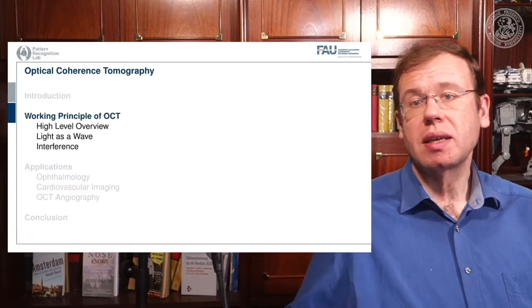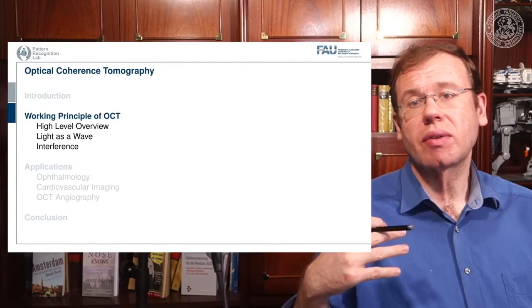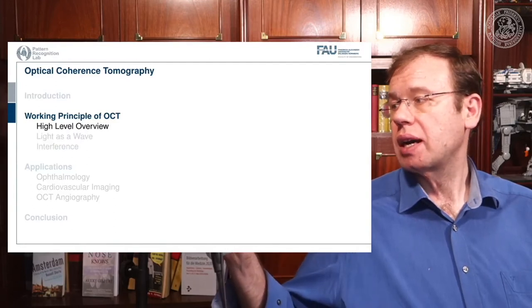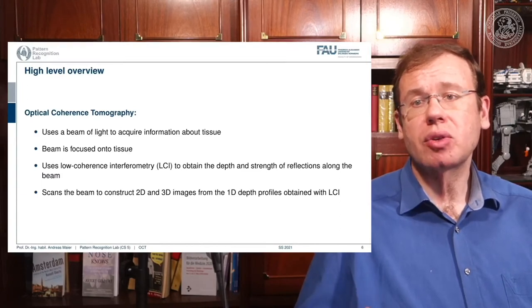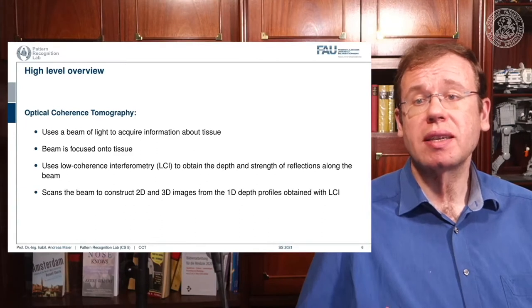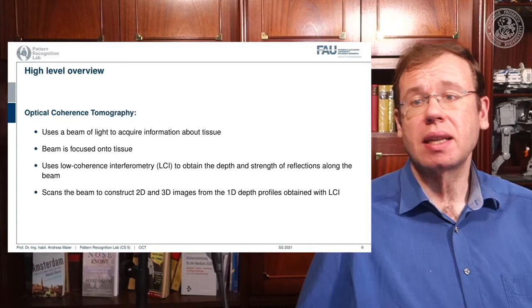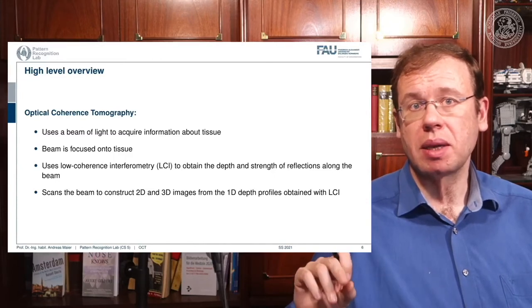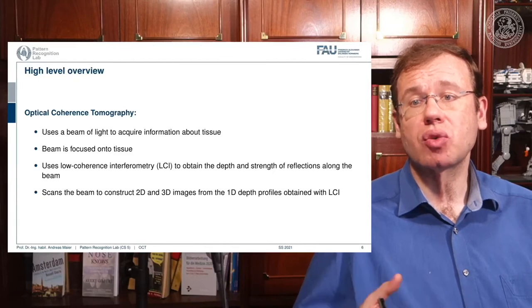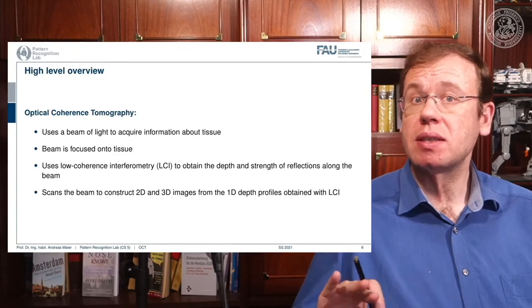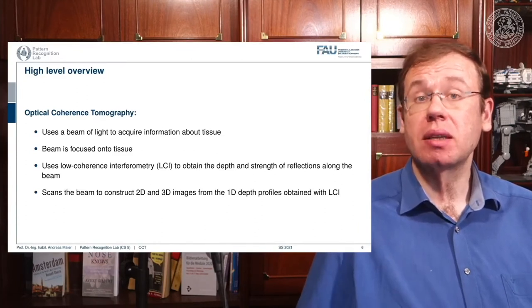The working principle of OCT is described at several levels. Starting with a high-level overview: OCT uses a beam of light to acquire information about tissues. The beam is focused onto the tissue, and we use low coherence interferometry — LCI — to obtain the depth and strength of reflections along the beam. Then we scan and reconstruct 2D or 3D images from 1D depth profiles, bringing back the concept of A-scan and B-scan from ultrasound.